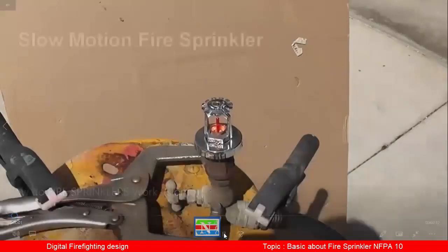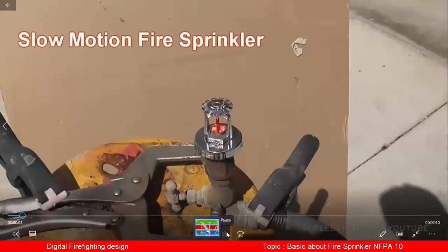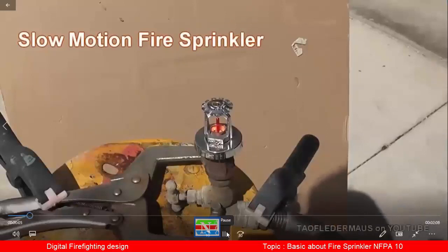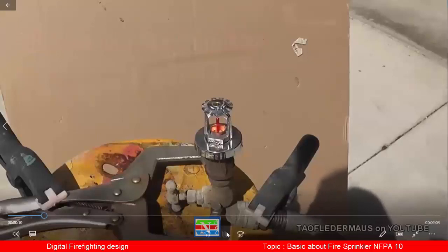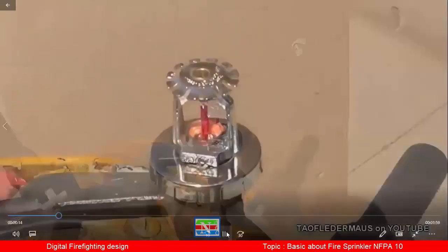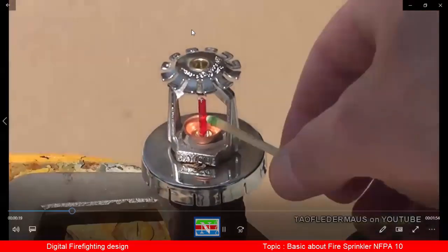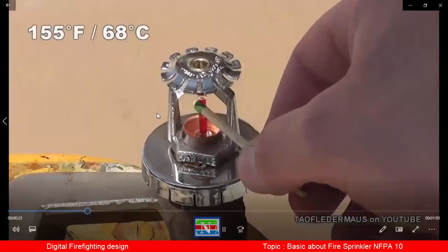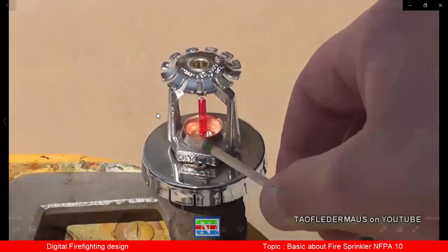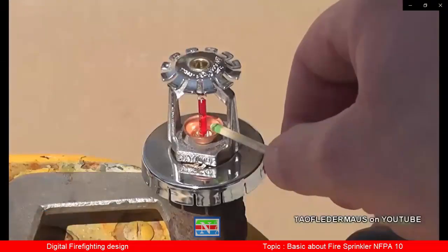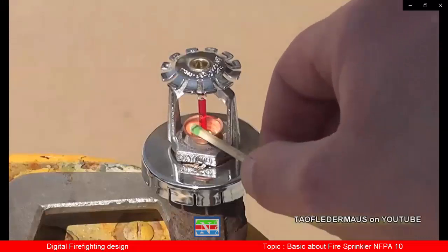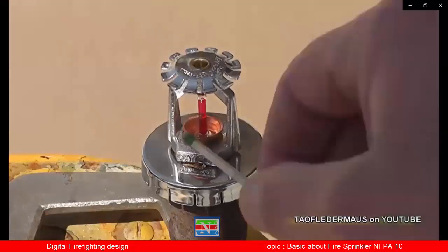Yeah. Today we're going to test it's a common fire sprinkler head. You've probably seen these in offices or buildings, warehouses, anywhere there's a fire protection system using these sprinklers. This particular one works when it gets to 155 degrees. There's a liquid in here that will expand in this glass ampule and break it and release this plug, which is called a pip, and it's a one-time deal.